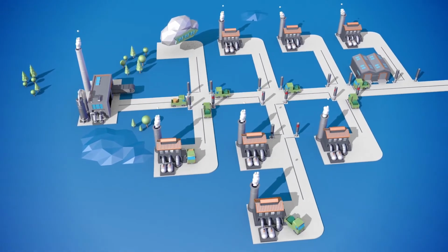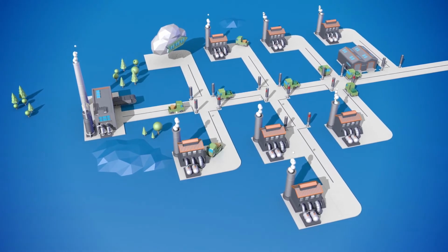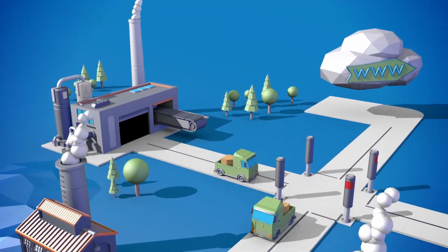Here is an example of data communication in real time. The PROFINET technology enables a data transmission rate of 100 megabits per second. This means a transfer of up to 100,000 telegrams per second. The telegram traffic is often greatest between the controller and the first switch.